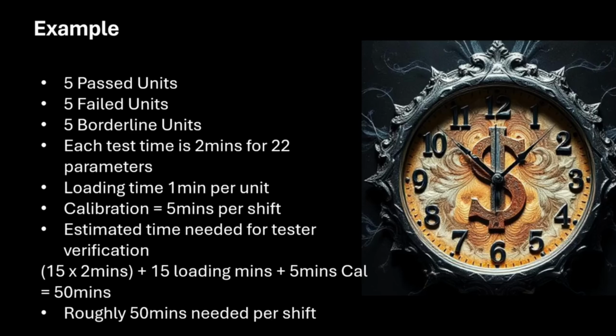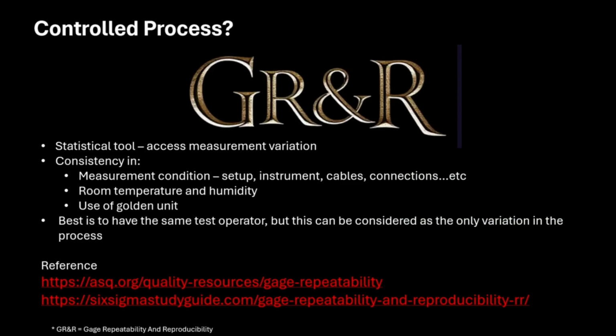Is that the time that you can afford to lose at the beginning of the shift? These are the questions that you have to ask, and then talk to your quality control engineers or product engineers to lock down the number of units that you need to verify your tester before you move on. I'm not sure how many of you have heard of this term called GR&R, gauge repeatability and reproducibility. It's a statistical tool to assess measurement variation. Even with the variation, there is some consistency in measurement conditions, such as your setup, the cable that you use from the instruments to your device under test, the instruments that you use on the rack, the cables, the connections, the environment, the room temperature and humidity, and the use of golden units. It's a control process that is mentioned in the GR&R process.